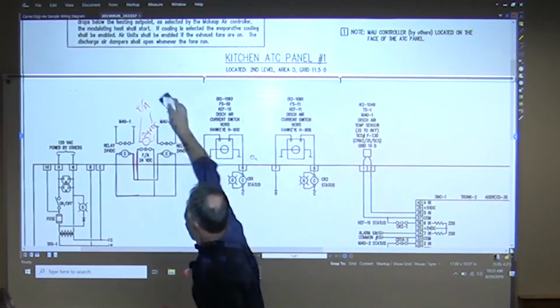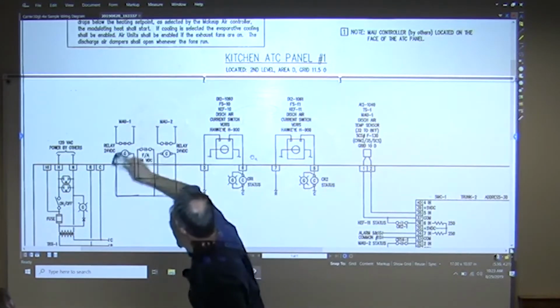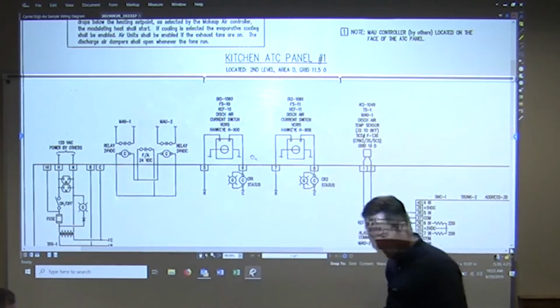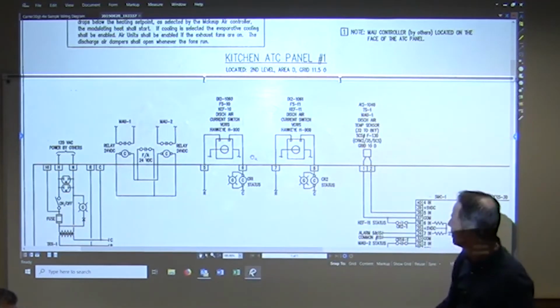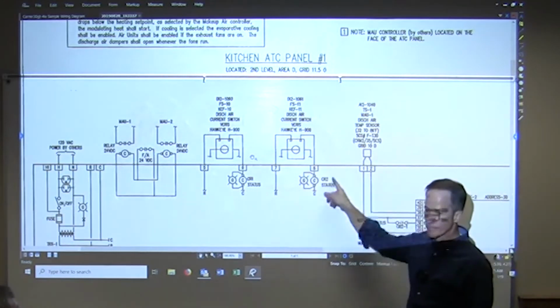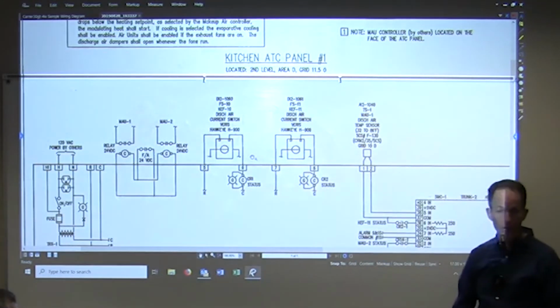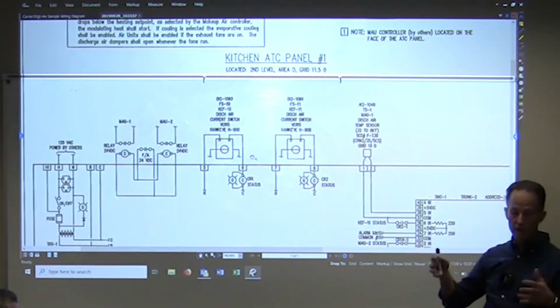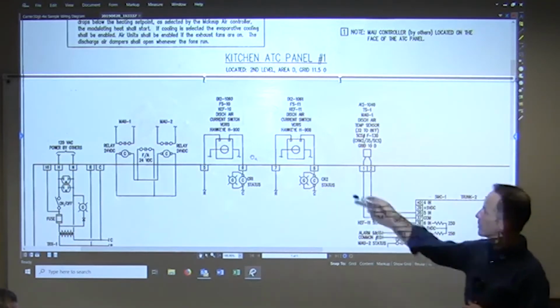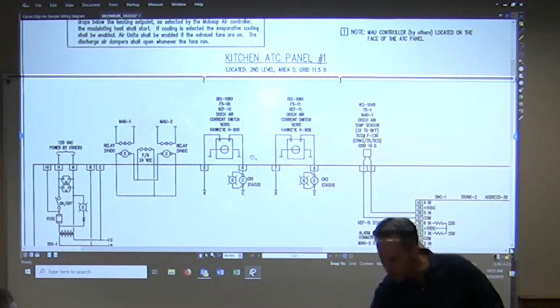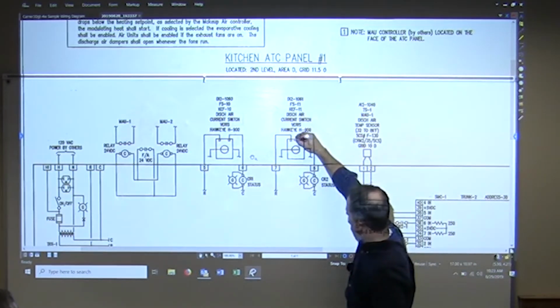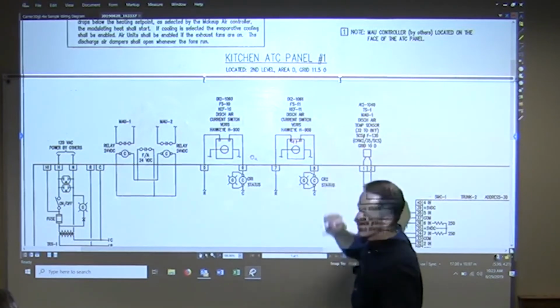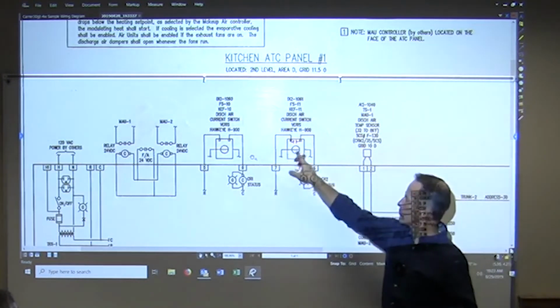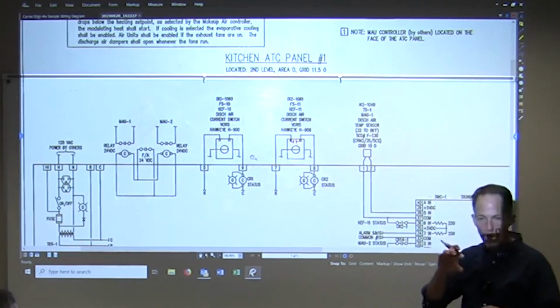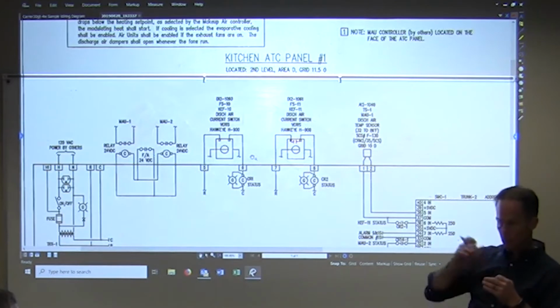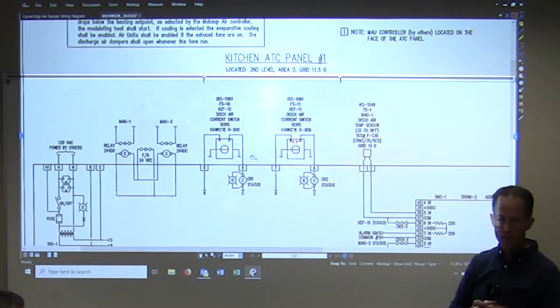What's going on right next door? This piece here. Short there. It's giving us a status of the fan running or not. Okay, so we're using a Hawkeye, which is a current switch, or in this case, it's a current transformer. It's a current switch in this case. It tells us that here. So that acts just like a relay contact, right? So you got a contact here that somehow, if current goes through that wire and we're monitoring it, that will turn on and off or switch that contact to the closed position.